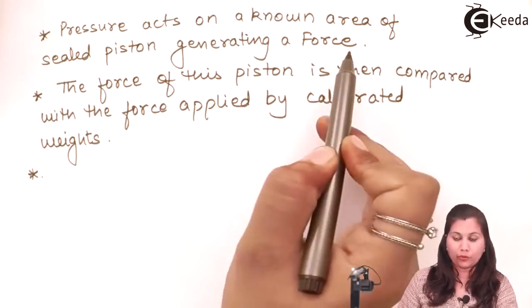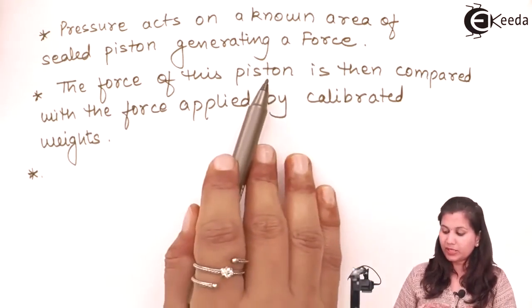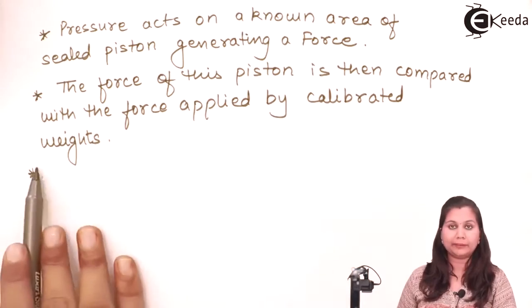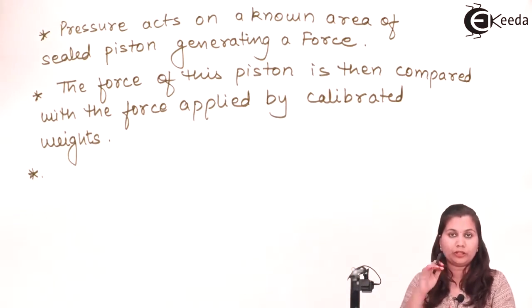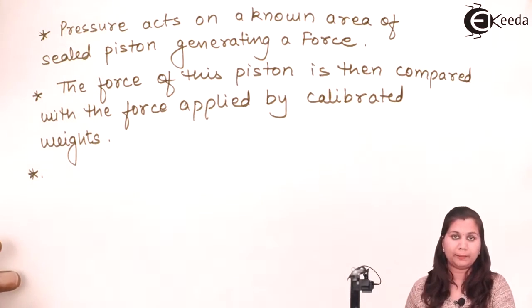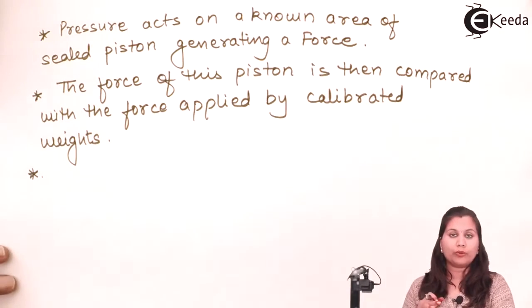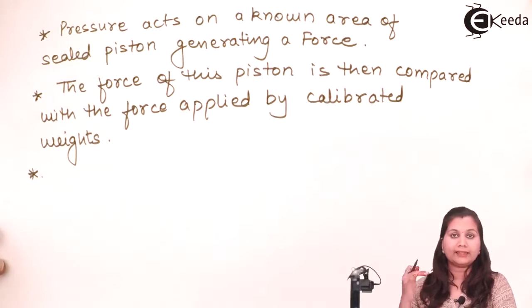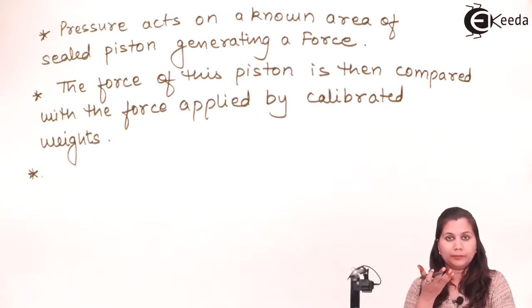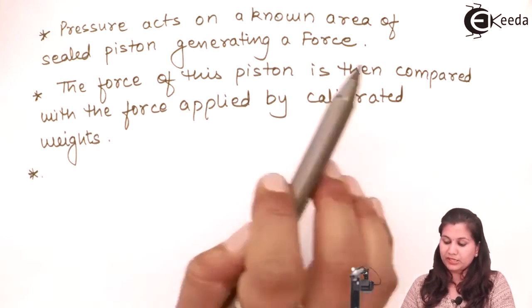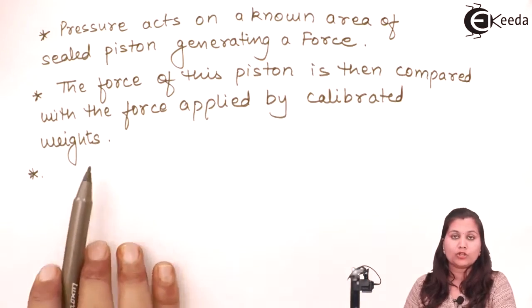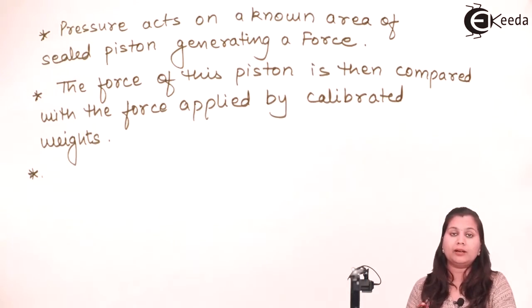So pressure is generating the force, and this force of the piston is then compared with the force which is applied by the calibrated weights. First we put known weights on the deadweight tester. Then we see how much pressure that weight applies. After that we apply pressure on the piston, and this pressure generates a force on the weights which are put on the deadweight tester. So the force of the piston is compared with the force applied by the calibrated weights. By balancing the forces we measure the pressure applied by the fluid or material, or we can calibrate a measuring device.